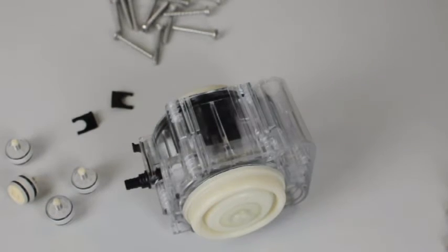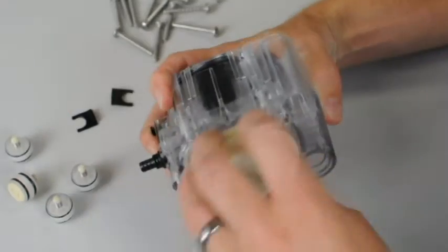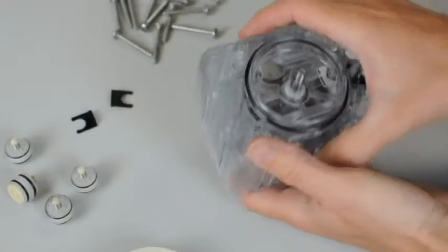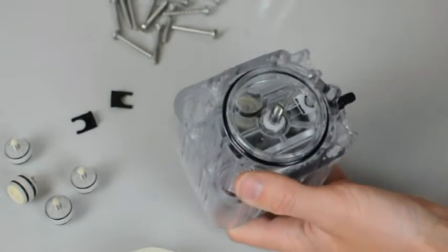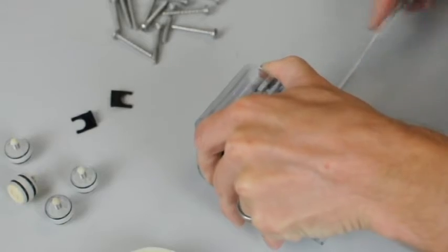Now if you'd like to remove the diaphragms, simply unscrew them from the pump. To remove the second diaphragm, use a flat head screwdriver in the slot here, and that will allow you to unscrew the second diaphragm.